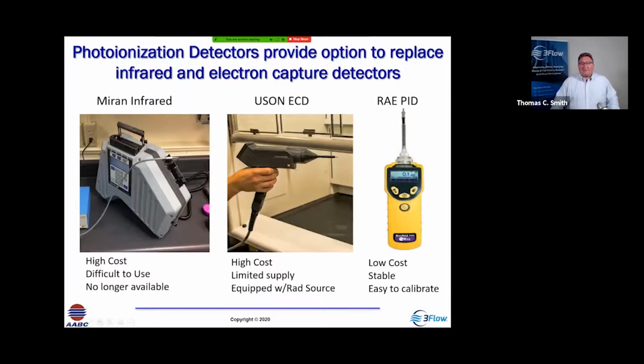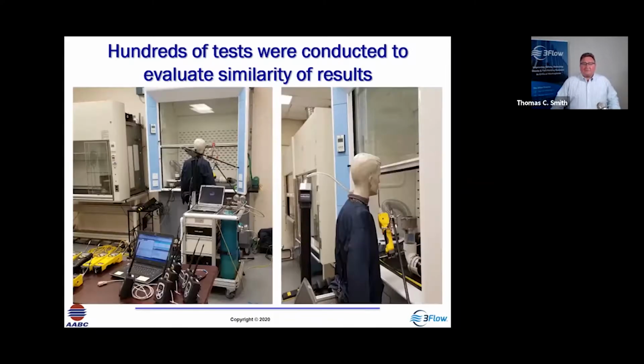As I mentioned, SF6, the detectors are very complicated and expensive. This unit is the infrared spectrophotometer, and it runs about $30,000 to $40,000. Well, nobody's selling these now, and they're not supporting their use anymore, so that's become an antique. And then we have still the use of the electron capture detector. They're about $30,000. Very finicky piece of equipment that requires an additional tracer gas plus a carrier gas in order for it to work. But we've found that those photoionization detectors are very inexpensive. They're about $3,000 each, have the sensitivity that's required to do the testing. They're much more stable and easier to use. So the combination of photoionization detectors plus the isopropyl alcohol gives us a good alternative.